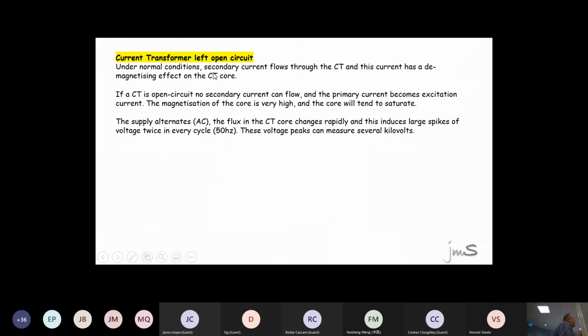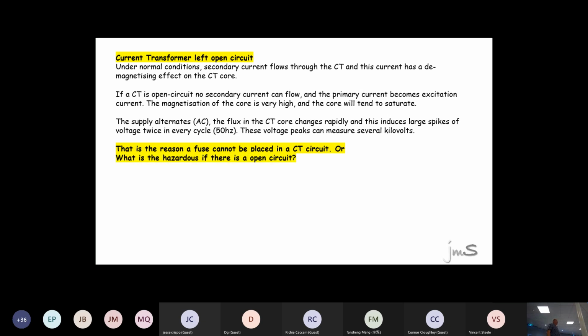When the transformer is left open, two things will happen. One, the CT windings will become so excited that they will start melting and overheating. The second one is a hazard. When you touch those two metal pieces, you might lose two fingers because of the high voltage over those two terminals. So you're going to get a shock because of that voltage, or the CT will burn out. So what must you do to prevent that? A, leave it open, or B, short them out when you disconnect an ammeter?